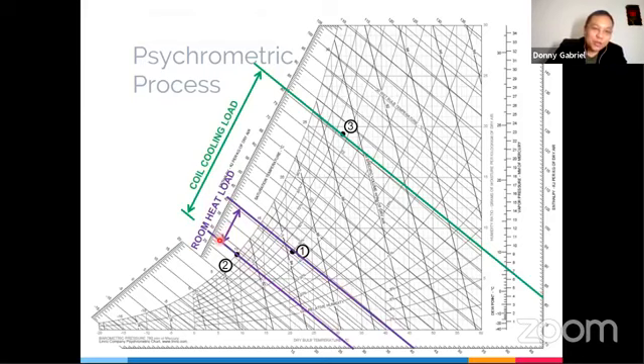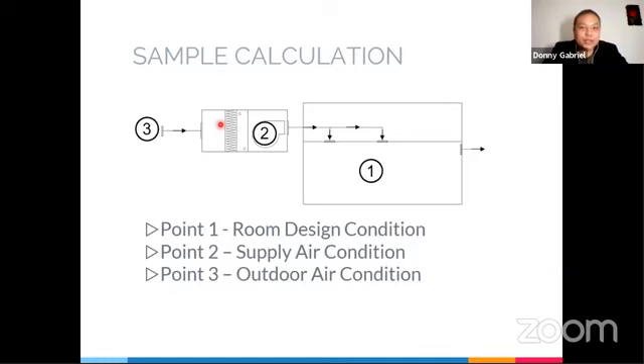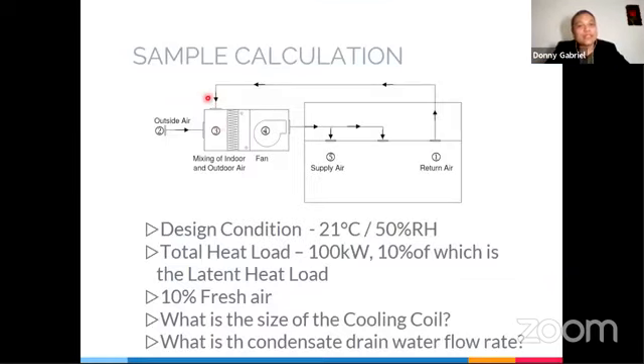This one is your room heat load. This one is your coil cooling capacity or your coil cooling load. Like Adrian was saying, if the coil load is equal to the room load, which means the coil is only using this much. So what is the scenario that your room heat load is equal to your coil cooling load? Your room heat load and your coil cooling load will be equal if the schematic is somewhat like this. If this outside air is taken out, deleted, your coil cooling load will be equal to your room heat load.